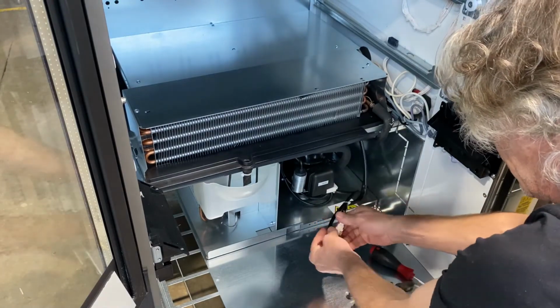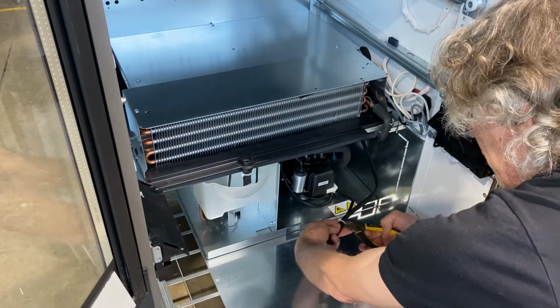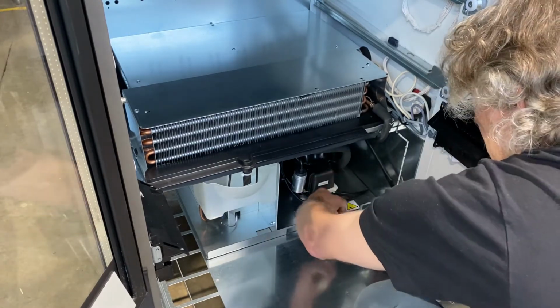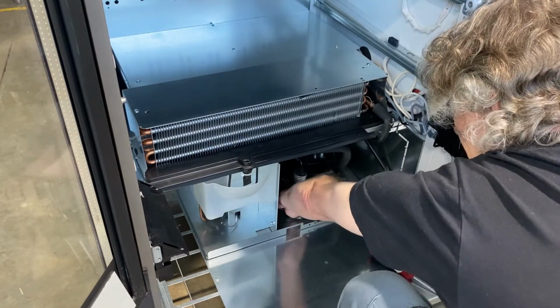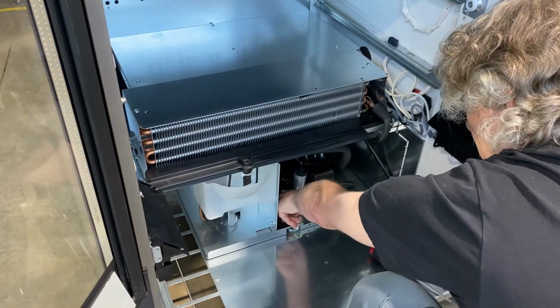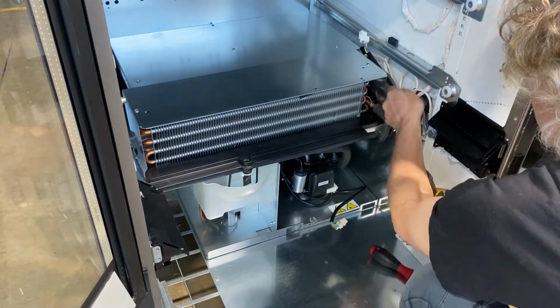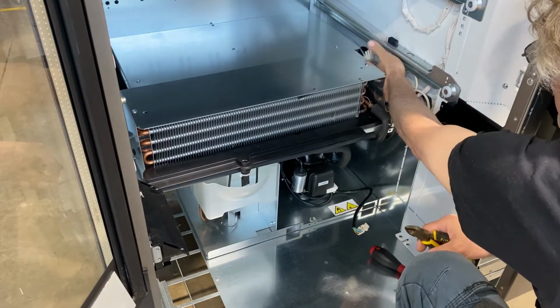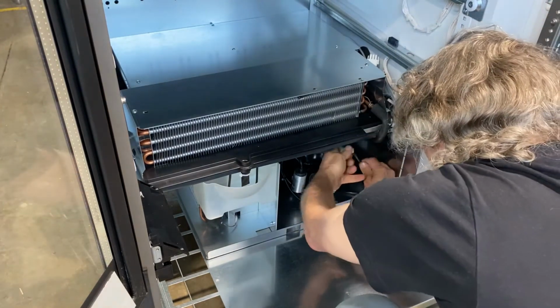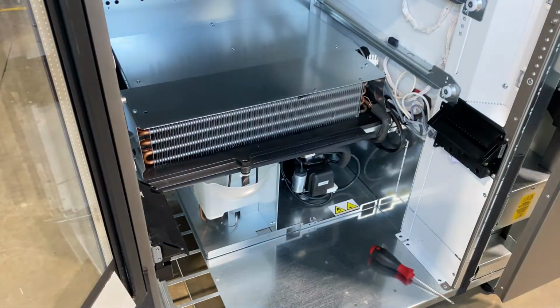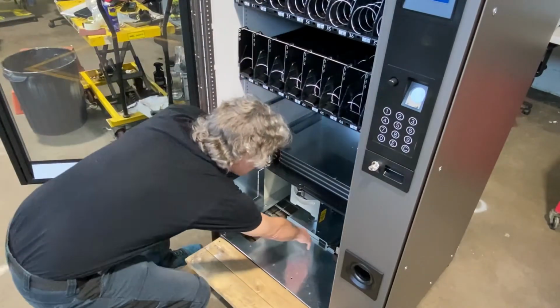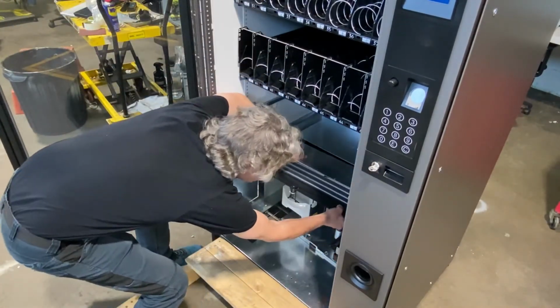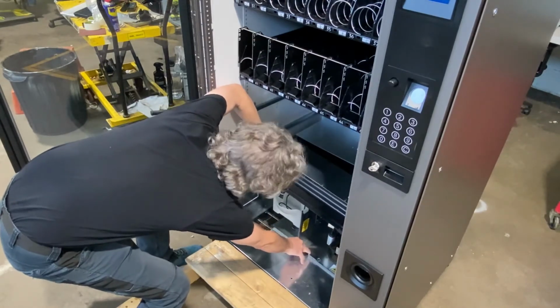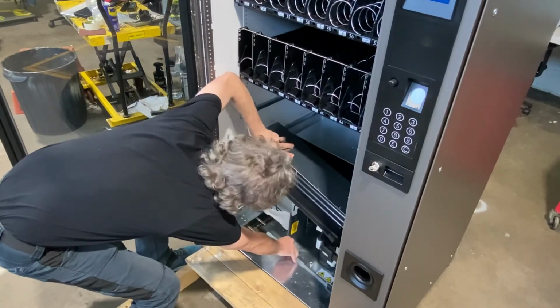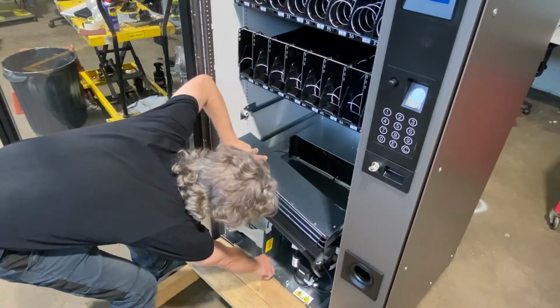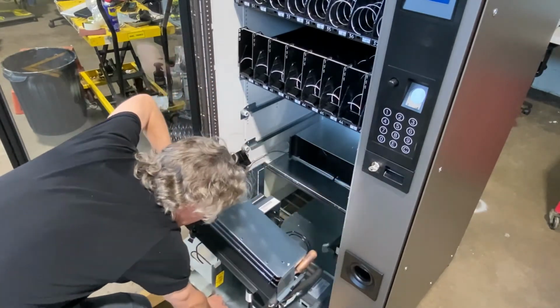Our power cord, disconnect. Again, we'll have to remove a cable tie. Tuck it back in, and set aside the power cord, a safe spot for us to slide the chiller out. Carefully slide the chiller out, both top and bottom at the same time. When approaching the vent sensor, give the evaporator coil a slight twist.